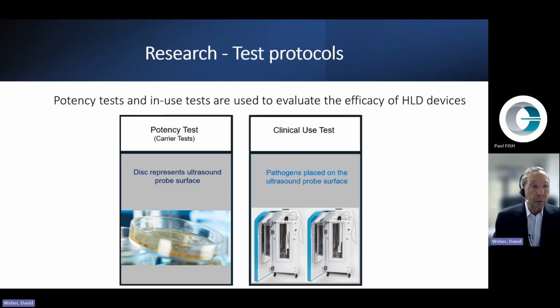Well, let's turn now and talk about research and test protocols. Potency tests and in-use tests are used to evaluate the efficacy of high-level disinfection devices. There are multiple types of test that can be used. The most common are a potency test that is carrier-based. Discs represent ultrasound probe surfaces and would be artificially contaminated, and then the system would be used to demonstrate decontamination. And then there is a clinical use test. Pathogens are placed on the ultrasound probe surface, run through the device, and decontamination is assessed.